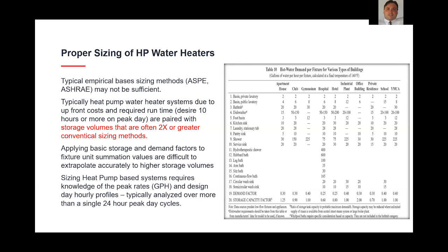So really what we need is an hourly profile. Just like we do with energy analysis, we need an hourly profile to analyze this under those peak design scenarios. And there's different ways to look at that, based on your known maximum peak gallon per hour rates that you have for the building, but that really needs to be extrapolated to an hourly profile.